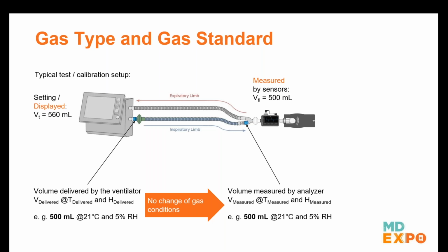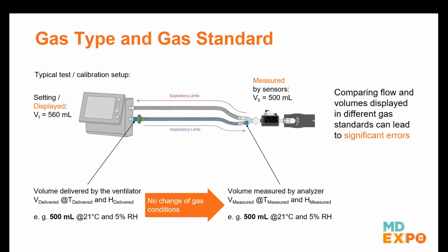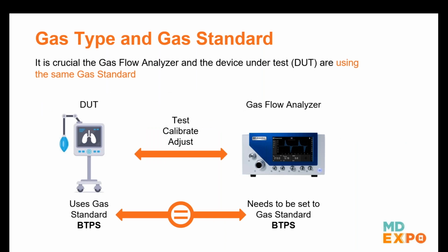We can take our measured value from our device and say, all right, there's a big error here because of this mismatch between gas standards, right? So if we set our analyzer to BTPS, it's the same as the ventilator, and now both of them are going to display the same volume, even though they're both actually measuring less. Does that make sense? So again, the big takeaway here is make sure that your analyzer is set to the same gas standard as the unit under test.